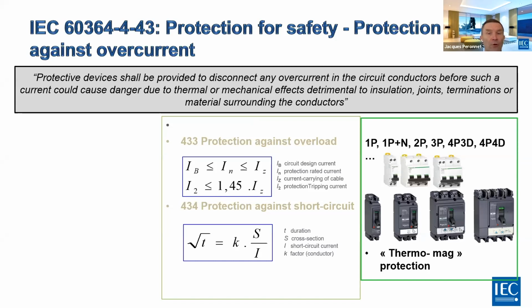Regarding the protection against overcurrent, this is part 443. A protective device shall be provided to disconnect any overcurrent in a circuit conductor before such current could cause danger due to thermal or mechanical effect, detrimental to insulation, joints, terminations, or materials surrounding the conductor. So this is usually made by an overcurrent protective device, which could be either a circuit breaker or fuses. On this, we describe in clause 433 the protection against overload, where we require the circuit to be protected against this overload. Usually, it's less than 1.45 times the rated current.